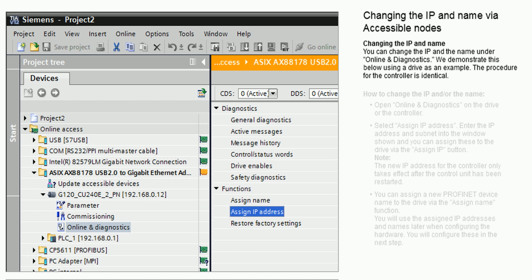Changing the IP and name. You can change the IP and the name under Online and Diagnostics. We demonstrate this below using a drive as an example. The procedure for the controller is identical. How to change the IP and/or the name. Open Online and Diagnostics on the drive or the controller.